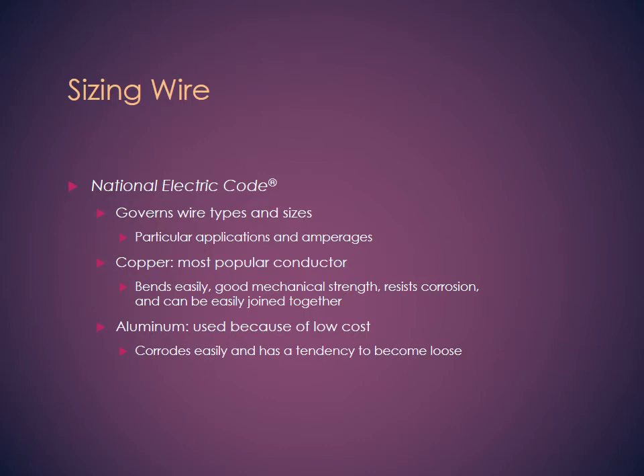So in National Electric Code, they dictate the wire size and type and what goes where. There are two big charts in the book that you can refer to when you need to. They are specific for the applications and amperage. In terms of conductors, I don't want to talk too much about it, but in the past we had aluminum. It was cheaper because there was a time when copper was expensive and not available, so they used aluminum. It corrodes easily. It has a tendency of becoming loose. Also, it fatigues easily, which means it breaks over time. It becomes very stranded. So it's better to use copper. Copper is a standard now, and it has good mechanical strength.